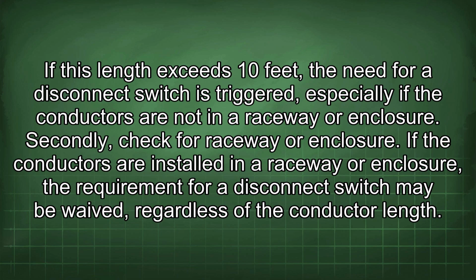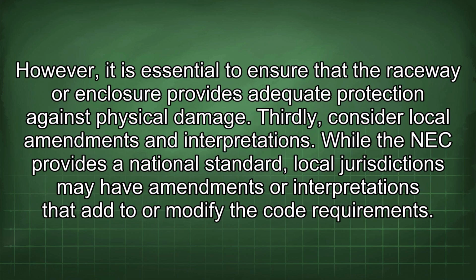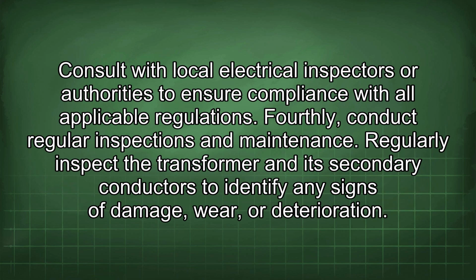If the conductors are installed in a raceway or enclosure, the requirement for a disconnect switch may be waived, regardless of the conductor length. However, it is essential to ensure that the raceway or enclosure provides adequate protection against physical damage. Thirdly, consider local amendments and interpretations. While the NEC provides a national standard, local jurisdictions may have amendments or interpretations that add to or modify the code requirements. Consult with local electrical inspectors or authorities to ensure compliance with all applicable regulations.